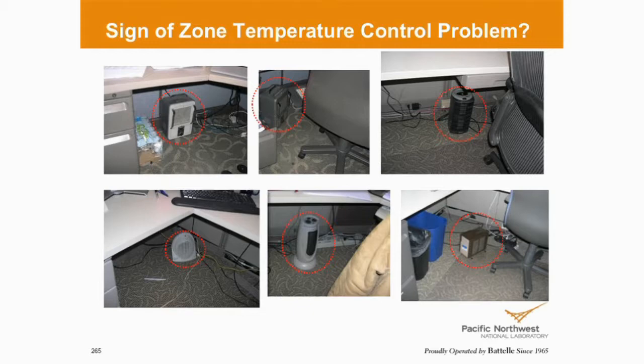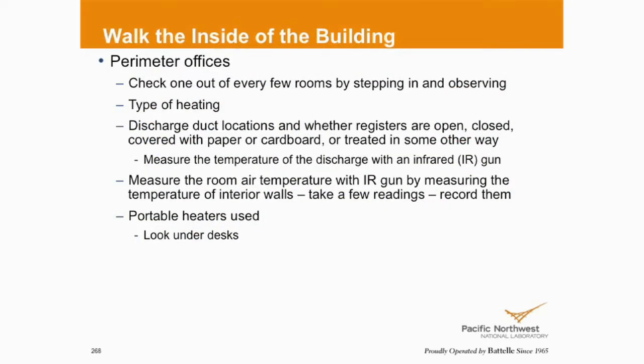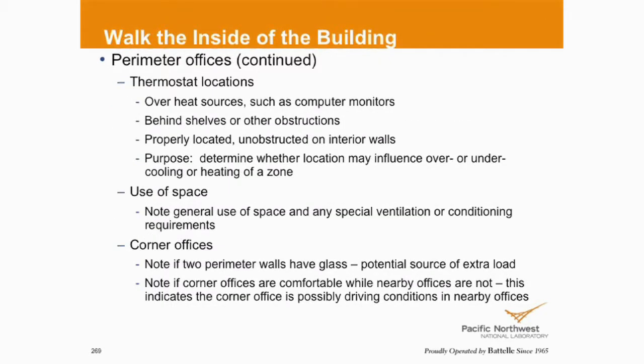And if we see this in the summertime, and it's more dominant in the summertime, what does that indicate? Too cold. Portable heaters, again, we saw in the previous slide. Thermostat locations, who's got it? Is it in one office and the VAV box is serving 5 or 6 offices and they're gone, they're on vacation, the lights are off, so it's cooled down to the point where everyone else is hot because the thermostat's in a cold room, or vice versa. Those are challenges. Don't really have good solutions. Well, we do have solutions, but they come with a cost.